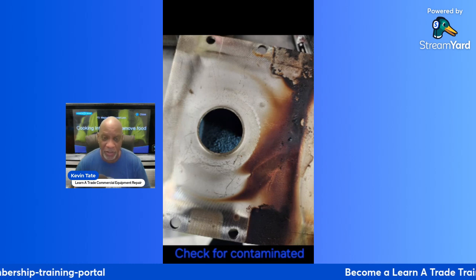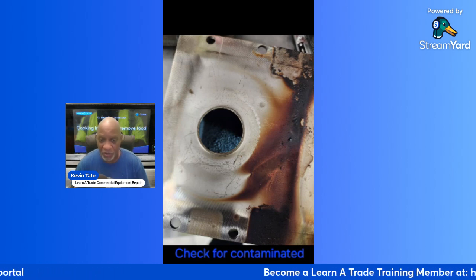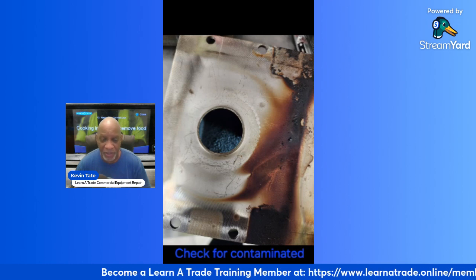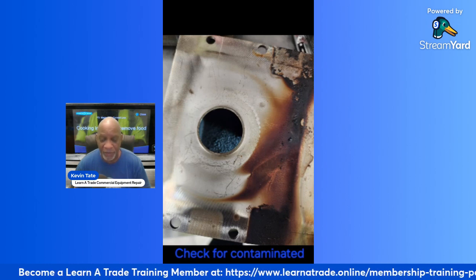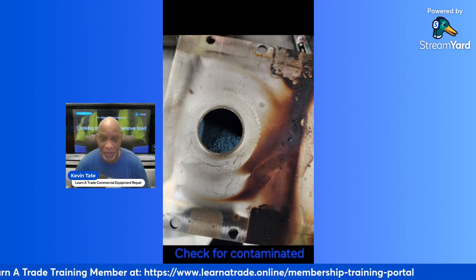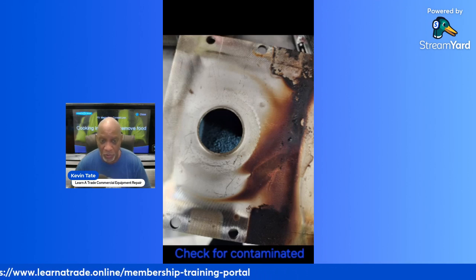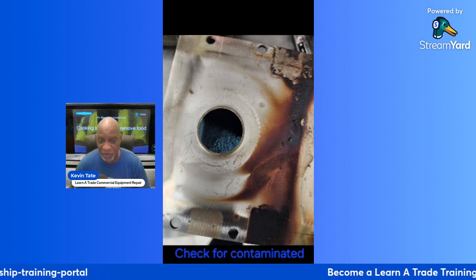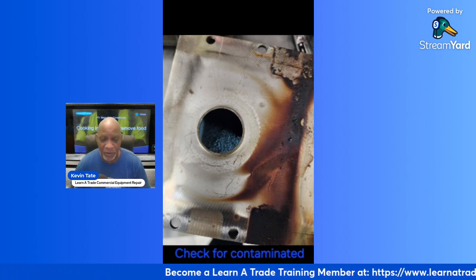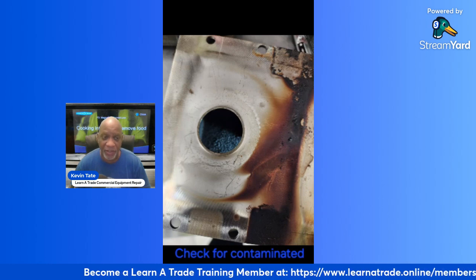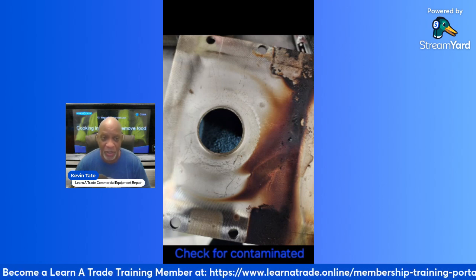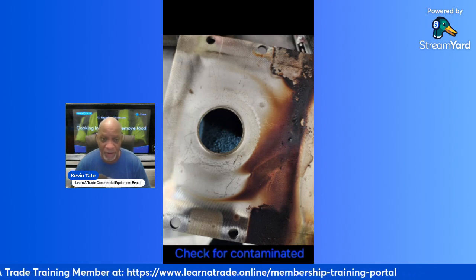If you clean it out as best as you can and you still see that there's contamination in there, then I recommend that you keep the machine down until you can come back with 2 new waveguides. And I'm saying 2 new waveguides because if one side is contaminated, it's pretty certain that the other side is going to be contaminated. So you might as well replace both waveguides.